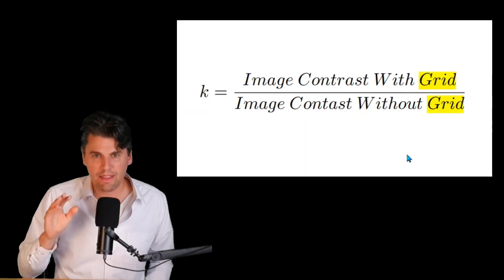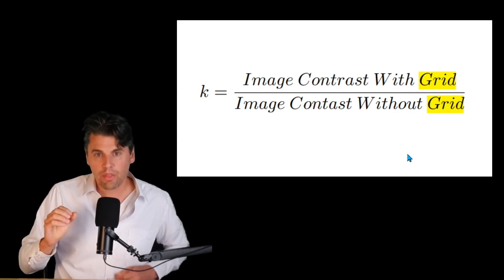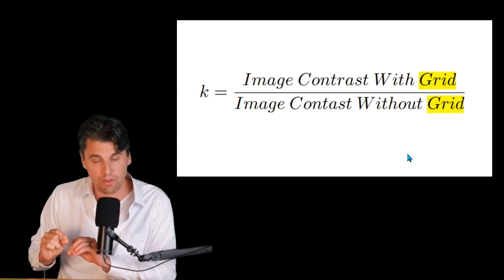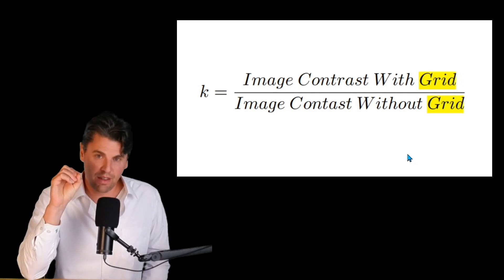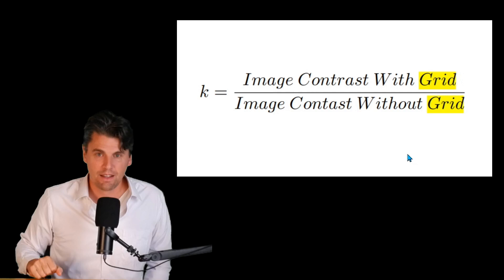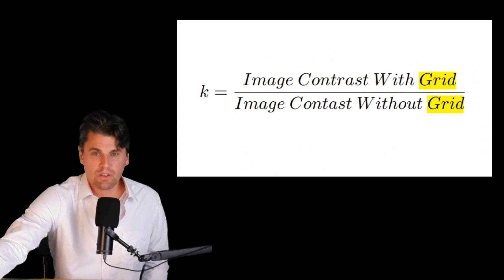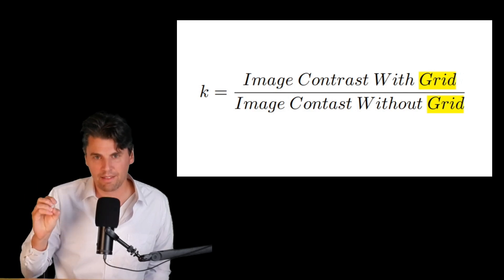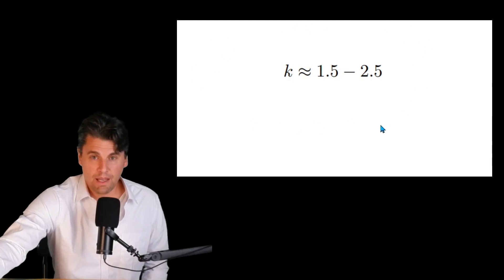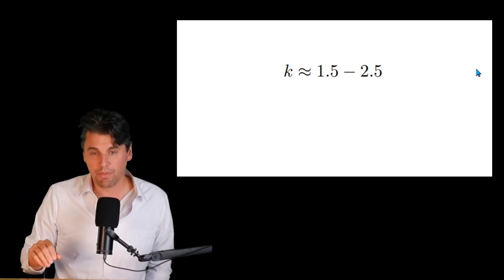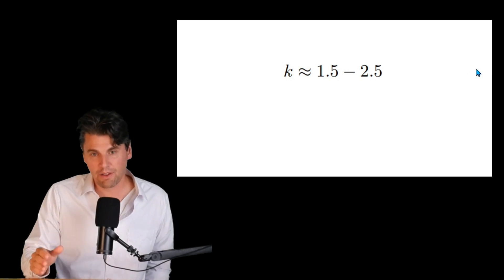Now let's talk about how we can quantify the improvement. By blocking scatter, the background haze is reduced, improving contrast in our x-ray image. We have an improvement factor K, which is the image contrast with the grid divided by the image contrast without the grid. You want K to be greater than one. Typically in x-ray imaging, K is on the order of one and a half to two and a half — your contrast improves by about a factor of two.